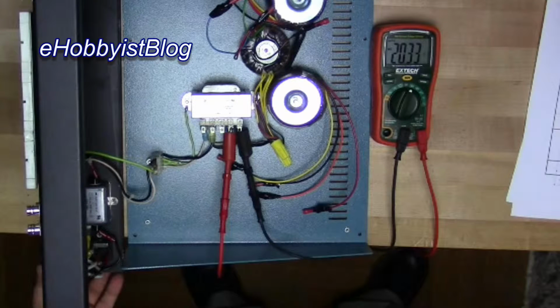In this video, I trimmed and stripped primary leads to the toroidal transformers, twisted primary wires of common polarity together and to the requisite hot and neutral lines, connected hot and neutral lines to the toroidal transformer, attached chassis ground to the lower half of the enclosure, attached the lower AC power connector shell to the lower half of the enclosure, and tested all the secondaries, recording their actual voltages.